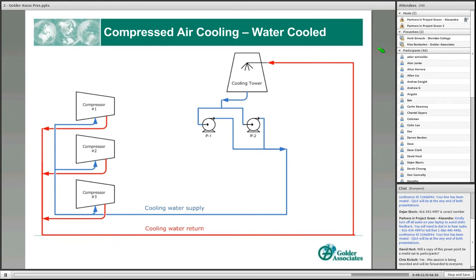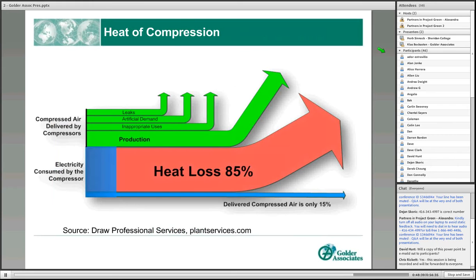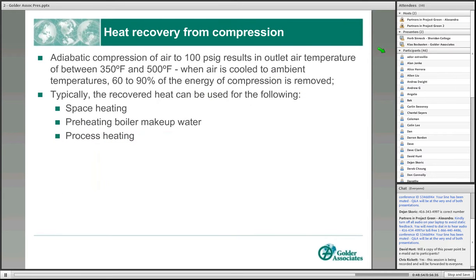And this is just a flow chart of 3 compressors with a cooling tower and 2 pumps distributing cooling water to the individual compressors. I won't dive into the details, but cooling towers are a common way of cooling compressors, especially in mid-size and larger plants. As Herb indicated before, 85-90% of the energy input is lost in the form of heat, unless it's captured for other uses. And there are many methods of utilizing that heat.